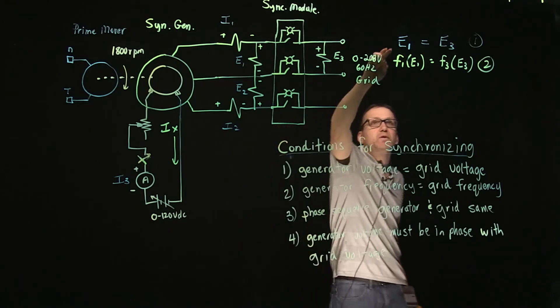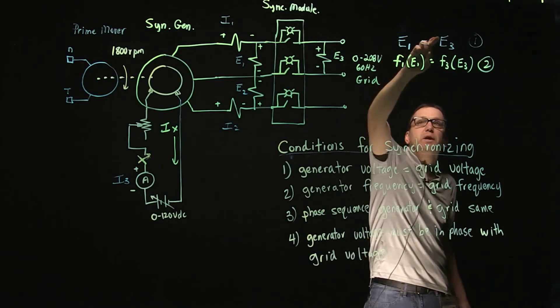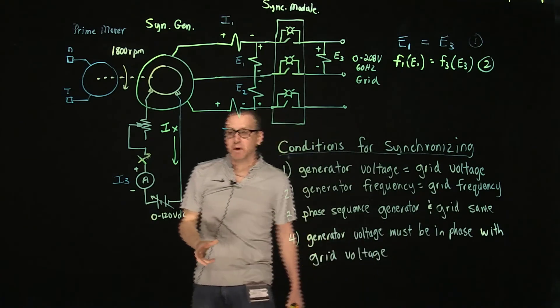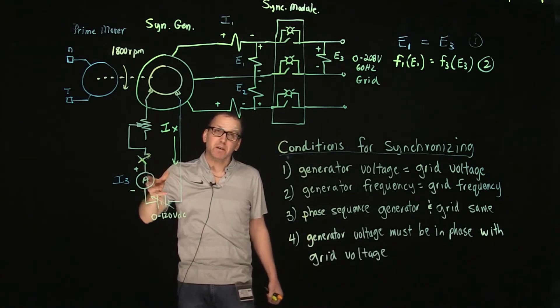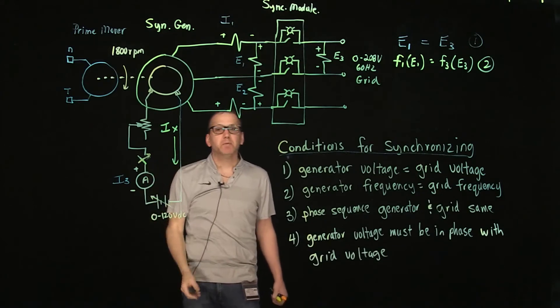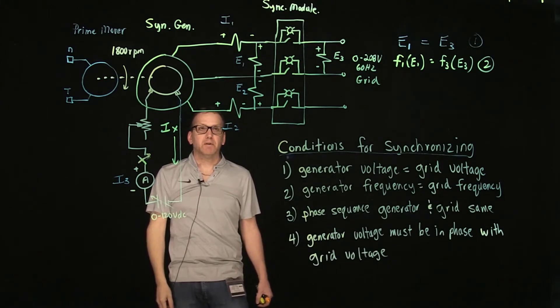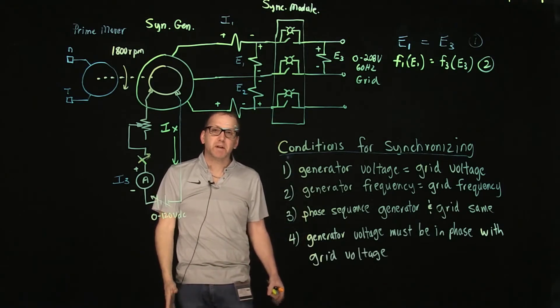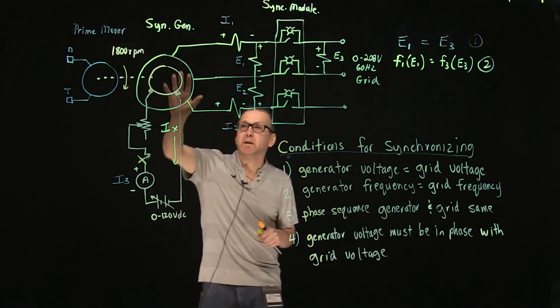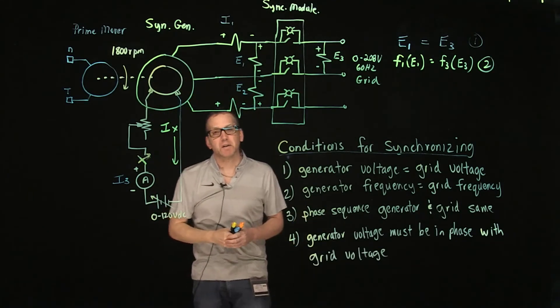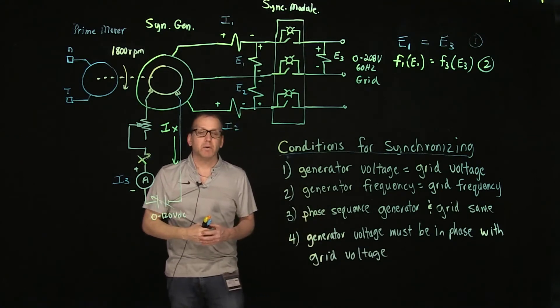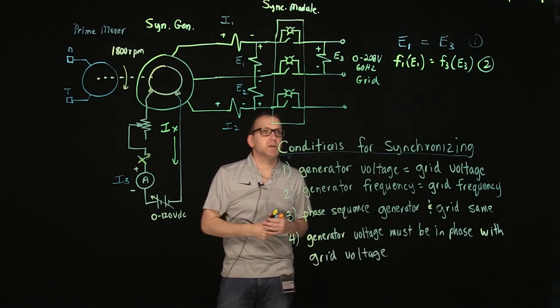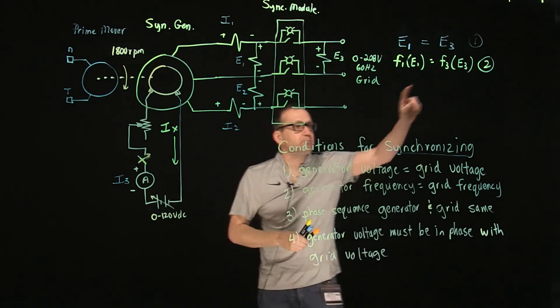In practice, we want the frequency of the incoming generator to be slightly higher than the frequency of the grid — for example, 60.1 or 60.2 hertz. The reason is that if the generator frequency is lower than the grid when we try to synchronize, it will come online as a load or a motor, which we don't want. So we want the frequency to be slightly higher than the grid frequency to satisfy condition two.